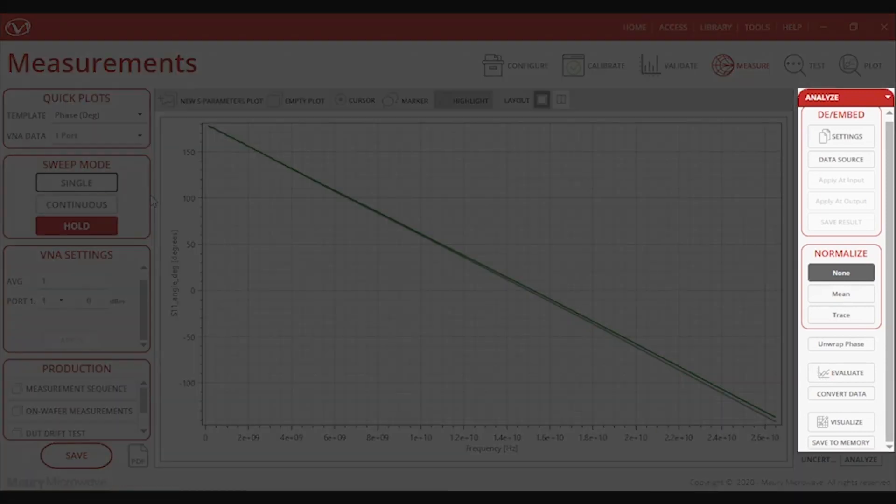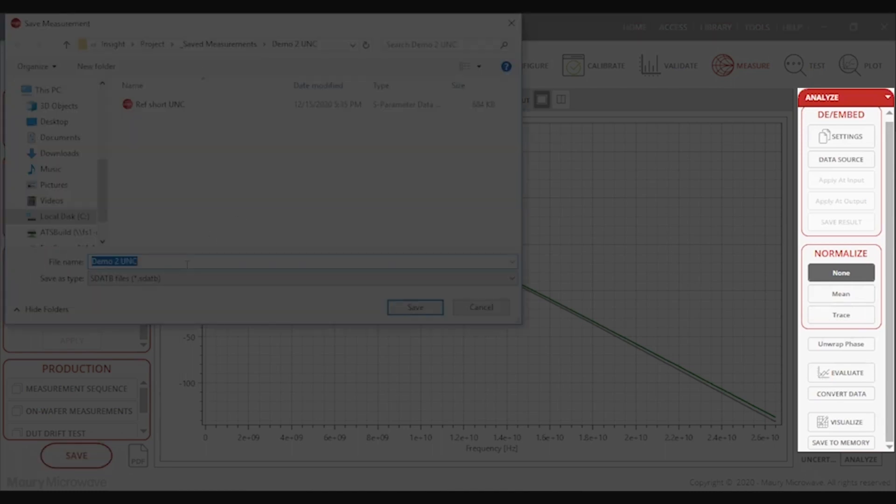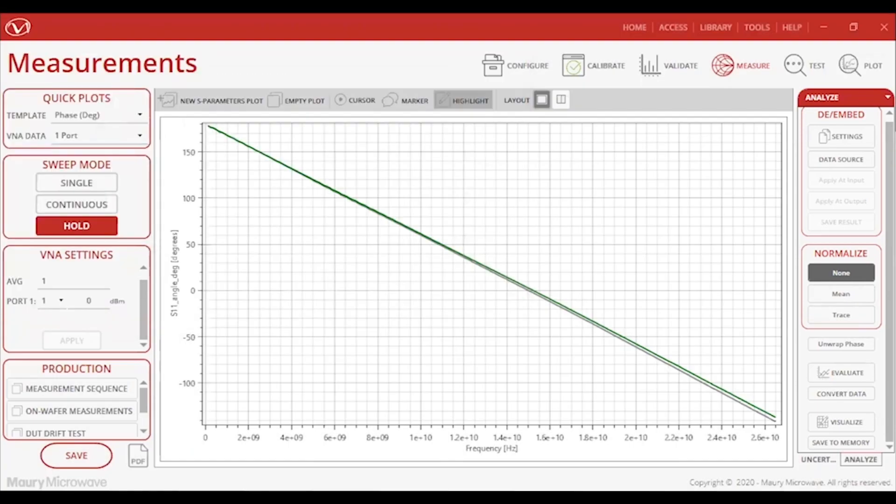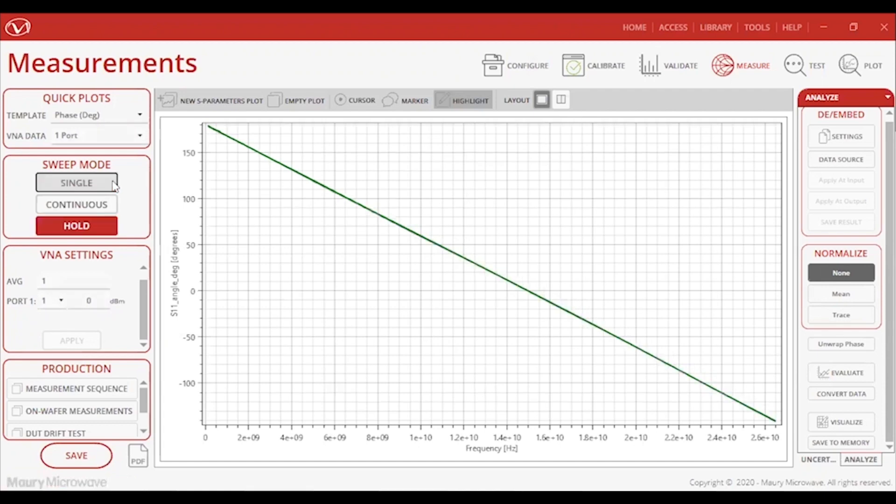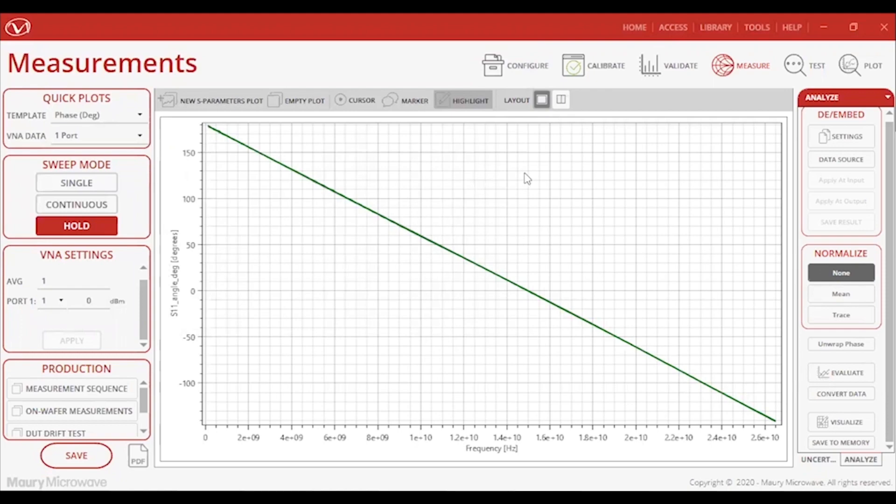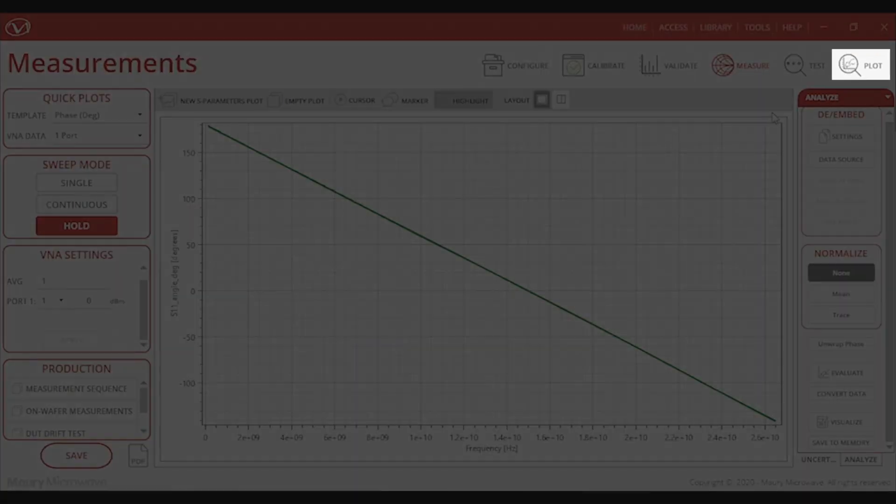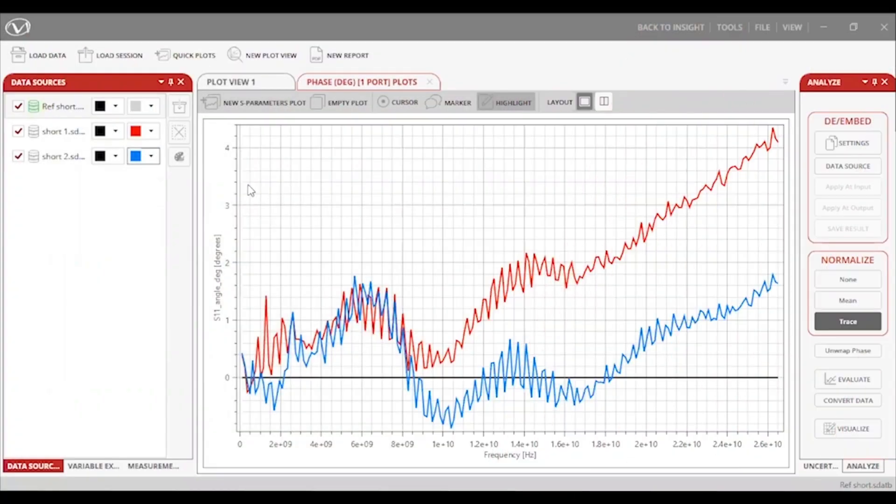The analyze section allows the user to de-embed, normalize traces, unwrap phase, and more. Before I move on to the plot module, I'll quickly obtain some data of a 24-inch Maury Stability Plus cable connected over to a short standard. Let's jump right into the plot module next.